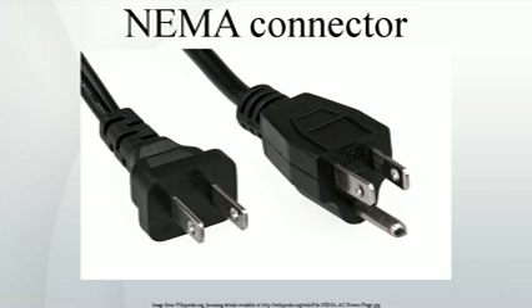The numeral preceding the hyphen in NEMA nomenclature indicates the configuration, that is, the number of poles, number of wires, voltage, and whether single or three-phase. A grounding type of device is described as 2-pole, 3-wire, or 4-pole, 5-wire, etc. A non-grounding device may be 2-pole, 2-wire, or 3-pole, 3-wire, etc. The numeral following the hyphen is the rating of the device in amperes. The number is followed by the letter R to indicate a receptacle, female connector, or the letter P to indicate a plug, male connector. As an example, the 5-15 is the common 125V 2-pole, 3-wire receptacle.